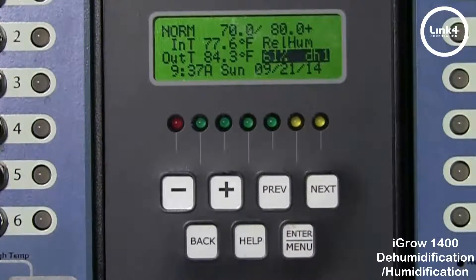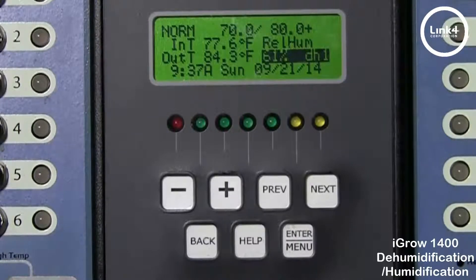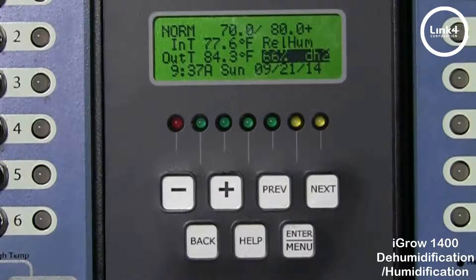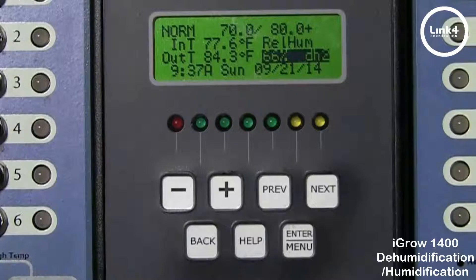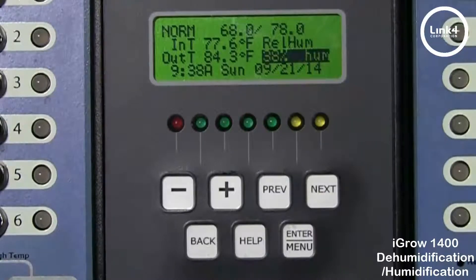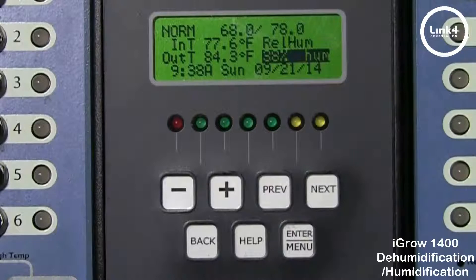We changed and calibrated the relative humidity reading to 61%, which forced the controller into DH1. We then changed the relative humidity reading to 66%, which is 5% above the setpoint, forcing the controller into DH2. And we changed the sensor to 38% humidity, which forced the controller into the humidification state.